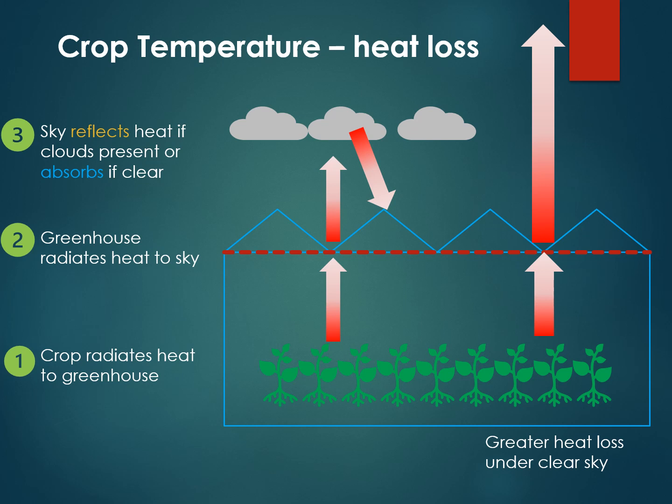So we know a crop is happy if it's cooler than the air in the greenhouse, because we know it's transpiring, right? If it's at the same temperature as up here, if they are equal, then this is going to end up overheating. There's no gradient, transpiration stops, temperature starts to spike. The crop could actually end up even hotter than the air in the greenhouse. So it's really important to think about, what is my crop temperature?